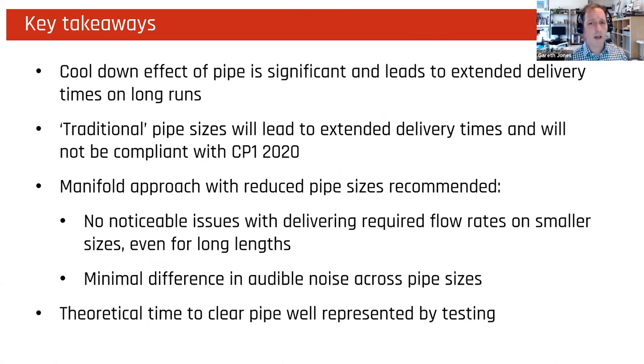So the key takeaways: the cool down effect of pipe is significant and can lead to extended delivery times on long runs. Traditional pipe sizes would lead to extended delivery times and will not be compliant with CP1 2020. We would recommend taking a manifold approach with reduced pipe sizes. You don't get noticeable issues delivering the required flow rates on smaller sizes, even for long lengths. There is a minimal difference in audible noise across the pipe sizes, and the theoretical time to clear the pipe is well represented by testing.